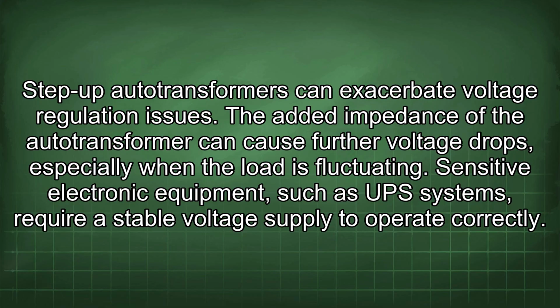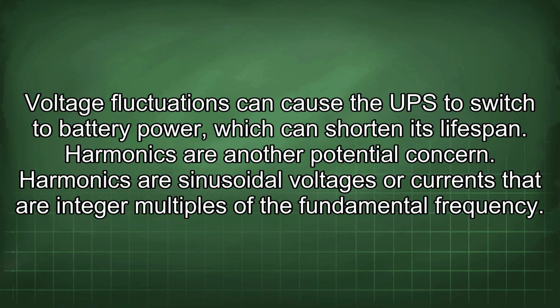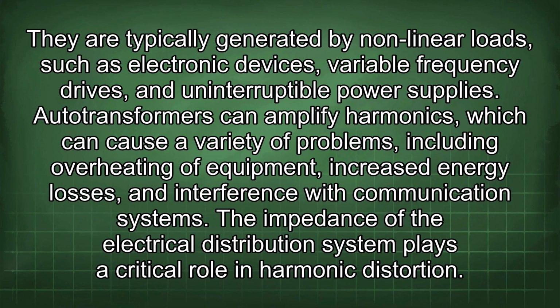Sensitive electronic equipment, such as UPS systems, require a stable voltage supply to operate correctly. Voltage fluctuations can cause the UPS to switch to battery power, which can shorten its lifespan. Harmonics are another potential concern. Harmonics are sinusoidal voltages or currents that are integer multiples of the fundamental frequency. They are typically generated by nonlinear loads such as electronic devices, variable frequency drives, and uninterruptible power supplies. Autotransformers can amplify harmonics, which can cause a variety of problems, including overheating of equipment, increased energy losses, and interference with communication systems. The impedance of the electrical distribution system plays a critical role in harmonic distortion.